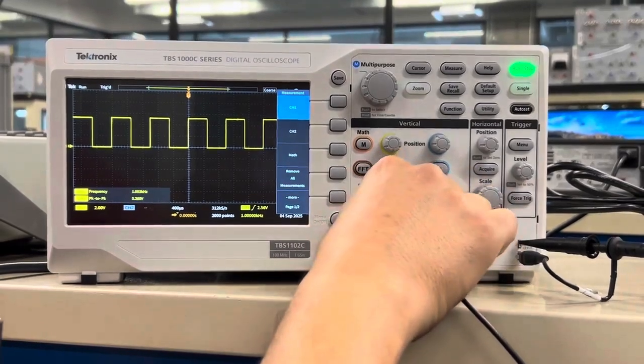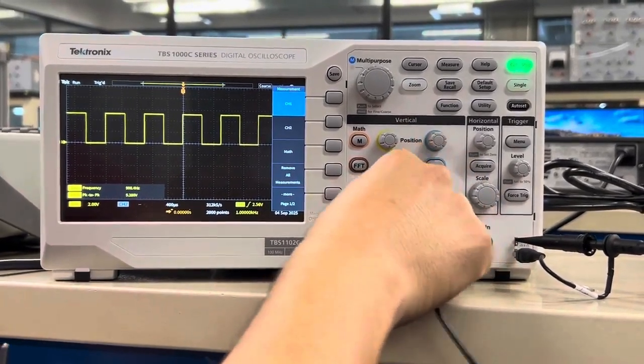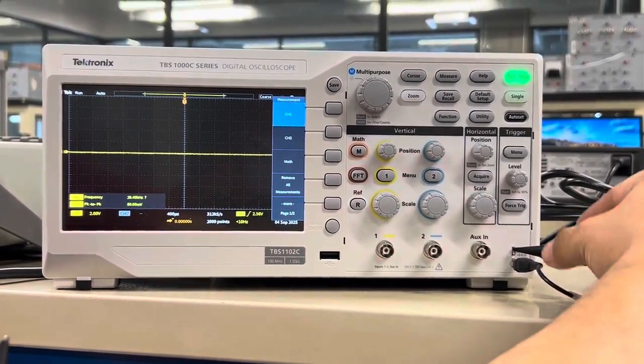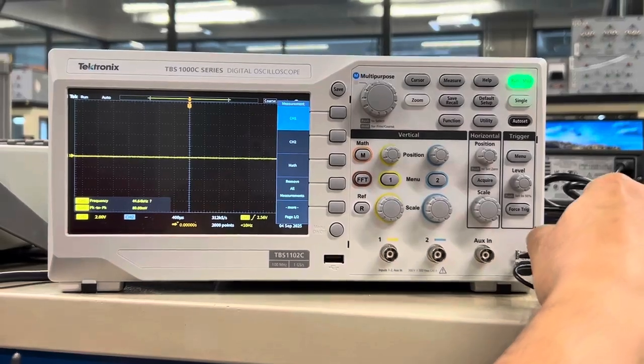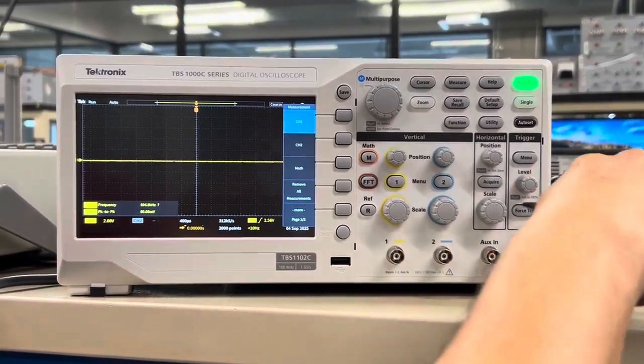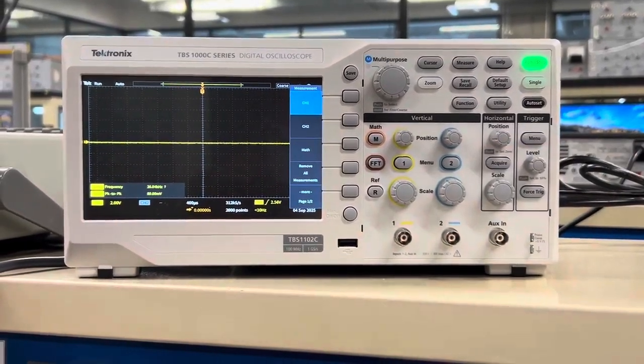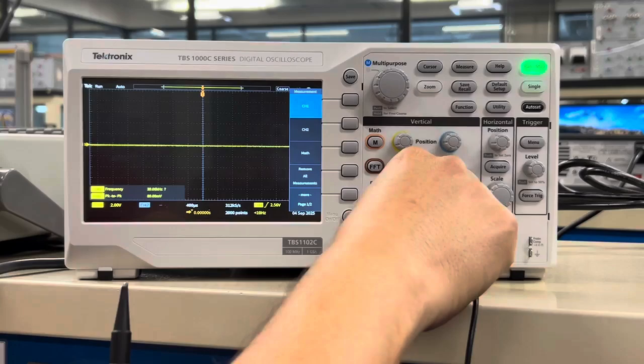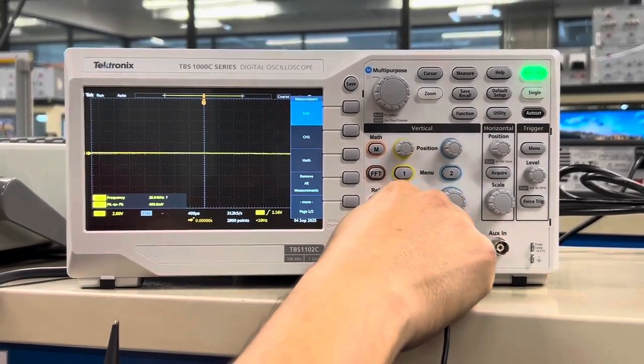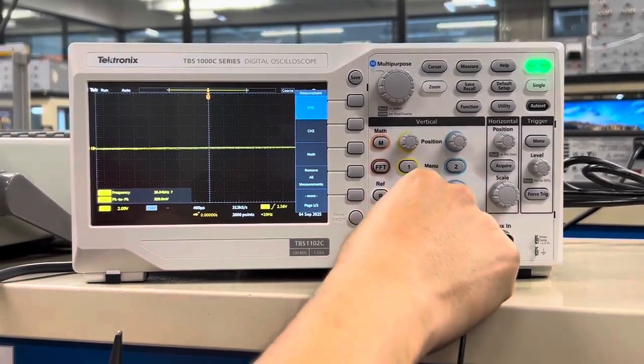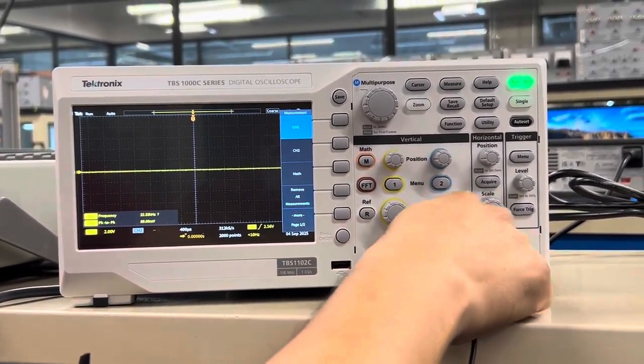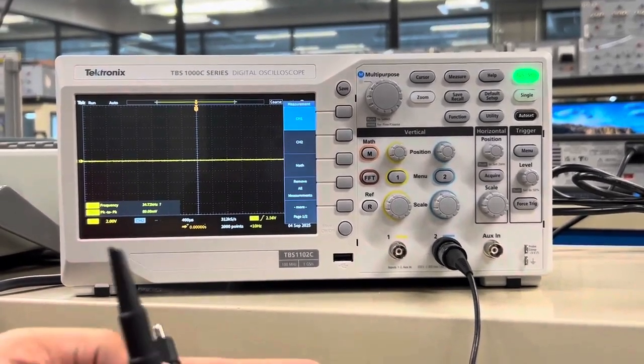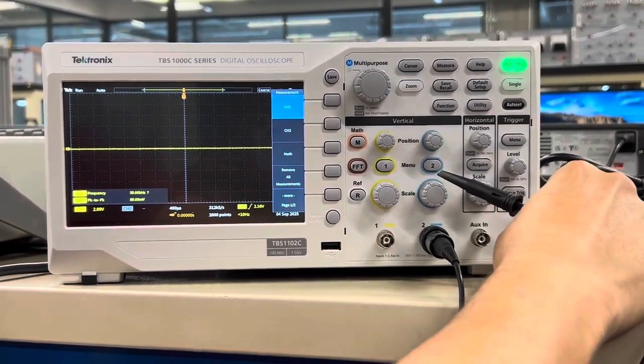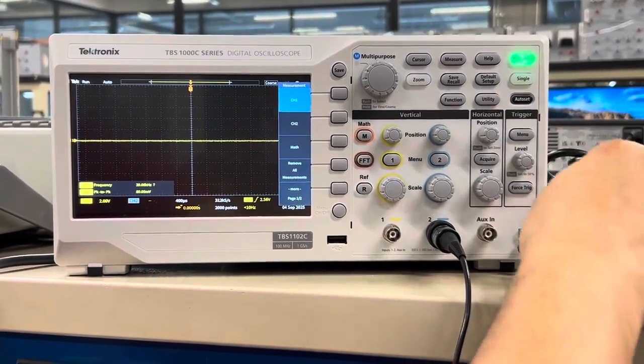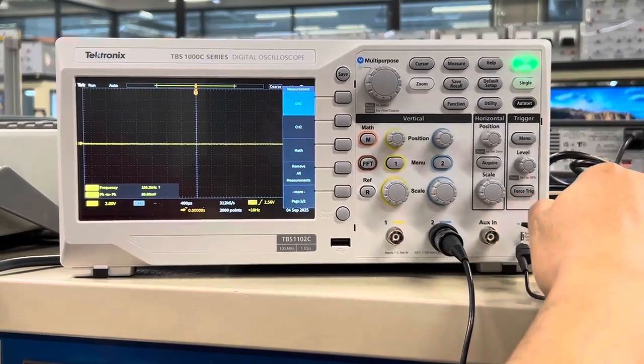We will disconnect. We're disconnecting the probe. It doesn't matter the order. We just need to be very careful with the hook. Gently pull, let it come back to its original position, and I'm connecting the other probe. Let's try channel 2 for a change. So we will connect it to channel 2. We will repeat ground to the bottom metallic connector, positive of the probe to the top metallic connector.